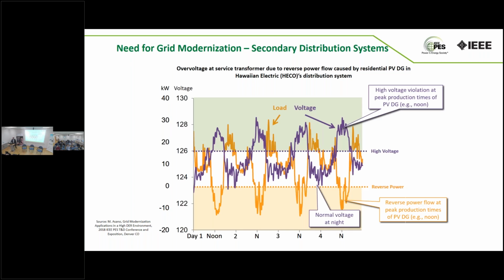Now let's look at voltage. Again, this is real data. In the US we use 114 to 126 volts for single phase residential service, and there's a range around 120 volts defined by the ANSI standard C84.1. Basically it says voltage shouldn't exceed 126 volts.